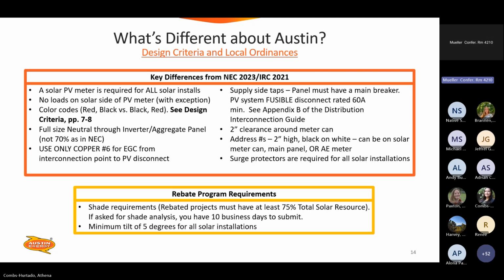You also need address numbers, like stickers, black on white, 2 inches high. This can be on the solar meter can, main panel, or the AE meter. Actually, ideally it would go on the AE revenue meter, but sometimes those meters are small and it doesn't fit. So you could put them on the PV meter can because the new cans are larger. You'll also be required to have a surge protector for all solar installations. So if it's an older service and a surge protector was not required, it will be required at our solar inspection.